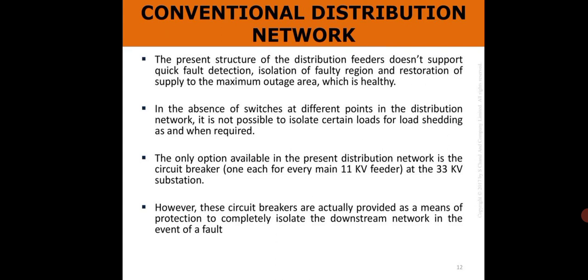Next, in the absence of switches at the different points in the distribution network, it is not possible to isolate certain loads for load shedding as and when required. The only option available in the present distribution network is the circuit breaker at the 33 kV substation. However, these circuit breakers are actually provided as a means of protection to completely isolate the downstream network in the event of a fault.